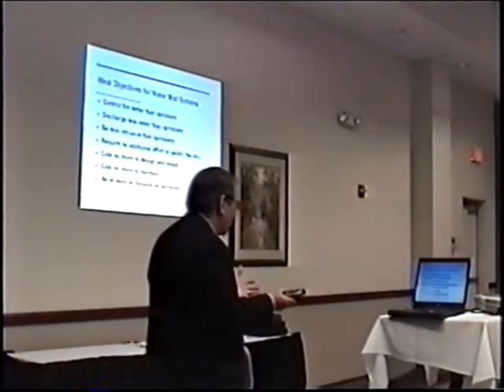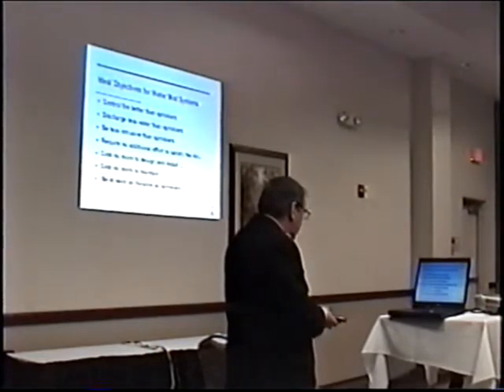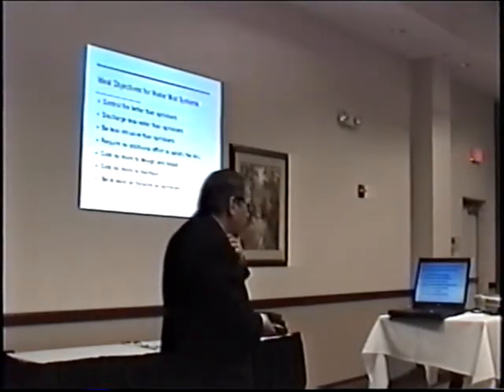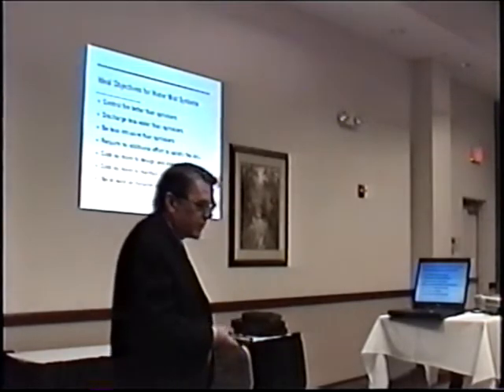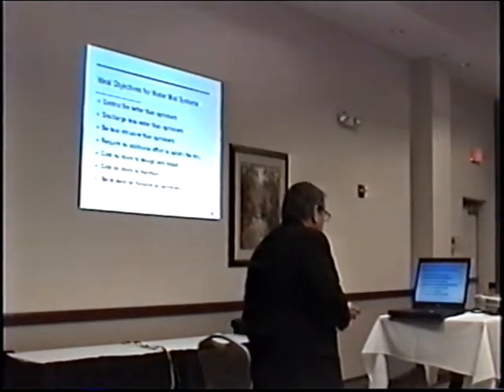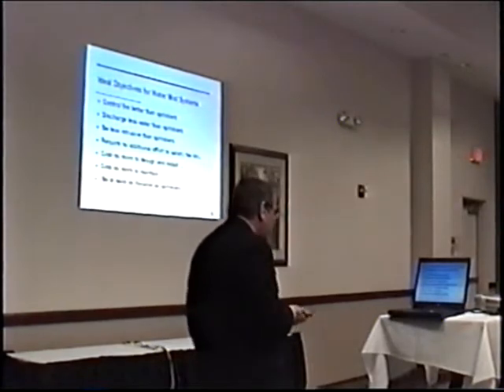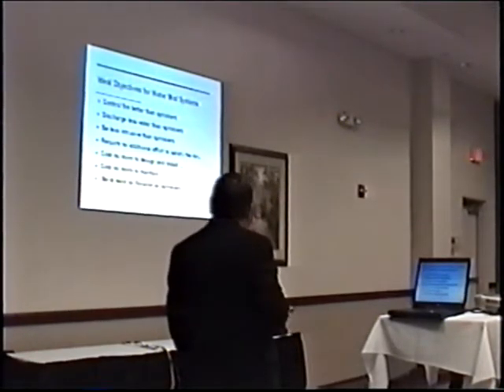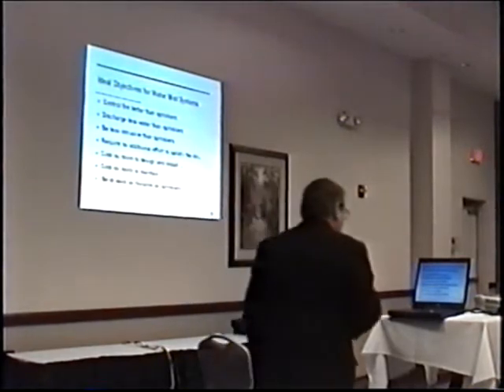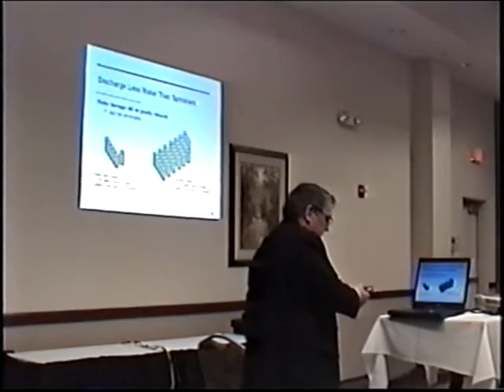I've listed the ideal objectives for a wonderful suppression agent. We'd like water mist systems to be able to control fire better than sprinklers, meaning using less water than sprinklers. We know sprinklers are intrusive in buildings, either the pipe that has to be installed in the walls or the sprinklers that have to be installed in decorative finishes. They're intrusive, so we would like something that's less intrusive than sprinklers. We'd like something that would be so acceptable to the authority having jurisdiction that there would be no difficulties in getting approvals. And of course, we'd like it to cost no more to design and install than sprinklers, cost no more to maintain, and be as reliable. So that's what we would like to have. I'm just going to run through which of those are kind of achievable and which are not.